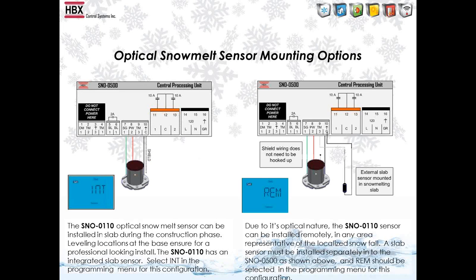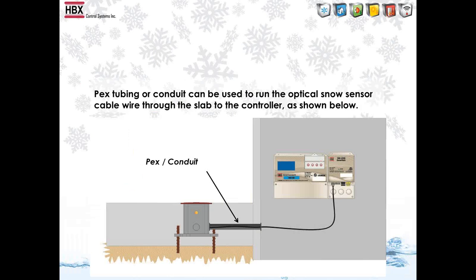When installing the snow sensor, make sure you are choosing the correct setting. If you are installing it in the slab, you would choose INT. If remote mounting the sensor, make sure you choose REM for remote mount. This slide shows that you run the cable from the snowmelt sensor to the snow control, and that cable can be run through a conduit.